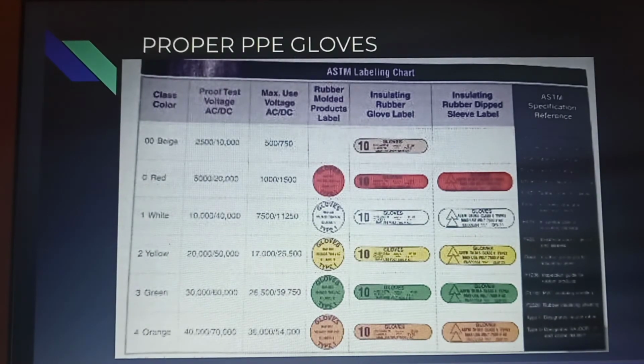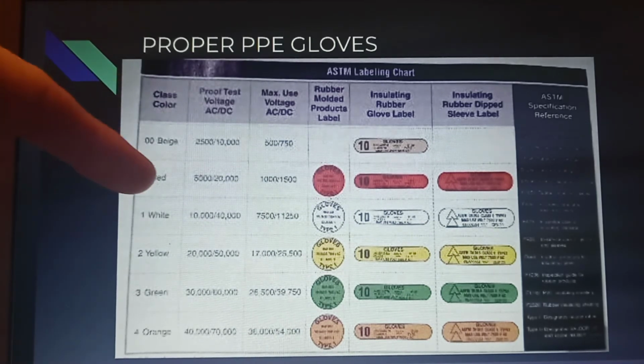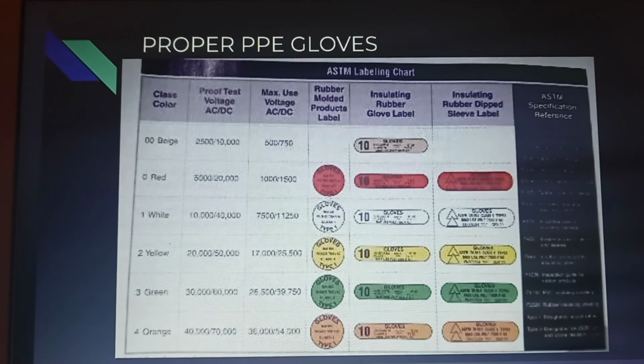And then this is the chart for the proper PPE gloves. We'll just read the red one, which is the second one, and it says proof test voltage. It went from 5,000 to 20,000 volts, or actually it's 5,000 AC and then 20,000 DC. And the max use voltage AC is 1,000 and the DC is 1,500. Rubber molded products label, it has a red label on it, and then the insulated rubber glove label is also red with a 10 on it. And then you also see the red label right there, dipped sleeve label as well.